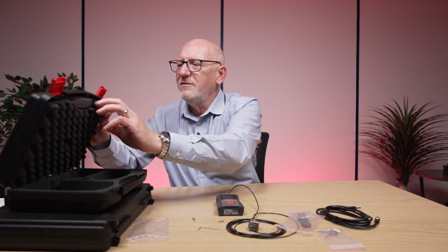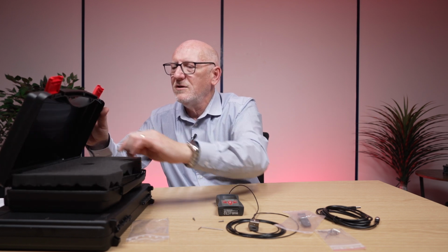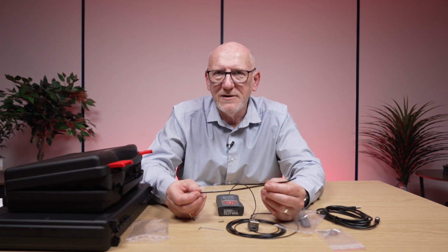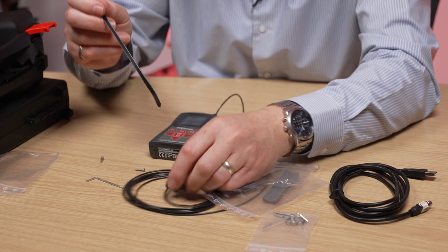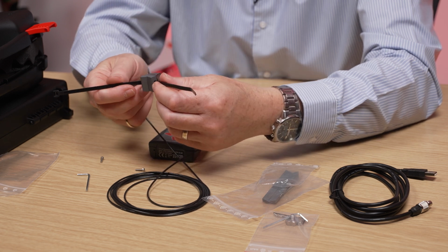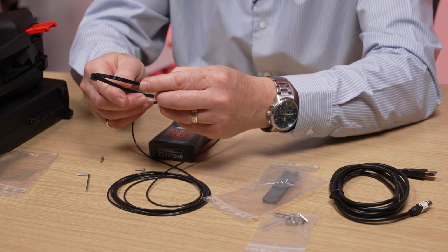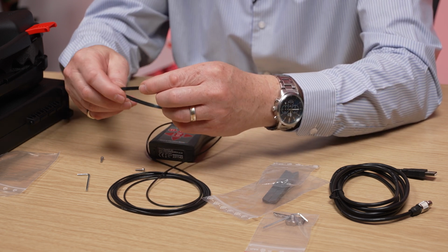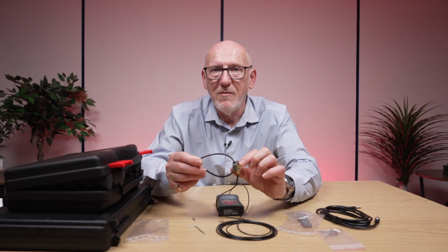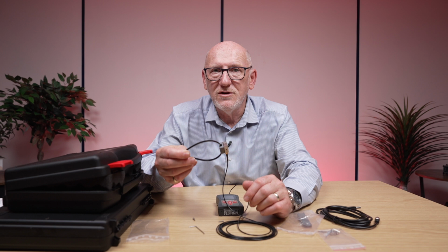And I would recommend that every time you use this kit, you basically have with you a number of cable ties, because this is the magic part. So what we're going to do, we can now put the cable tie through that block, and this will now allow us to tighten this whole accelerometer, using that block, hard against the tool.